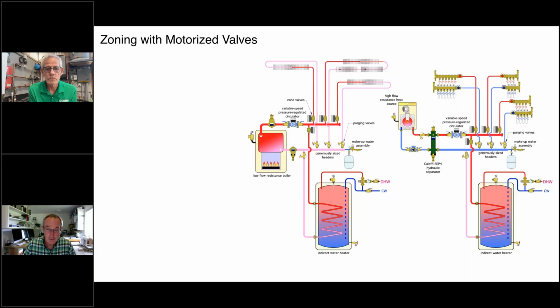Again, 3 zones of fin tube, 1 zone that is an indirect water heater. We've got separate components for air separation, dirt, and magnetic particle separation here. Over here, we've got a modulating condensing boiler. It's generally going to have a higher flow resistance. So to create hydraulic separation between the boiler circulator and this variable speed circulator, the hydraulic separator will do that for you. So the geometry, if you compare this to the geometry of the systems with the zone circulators, you'll see they're very similar.